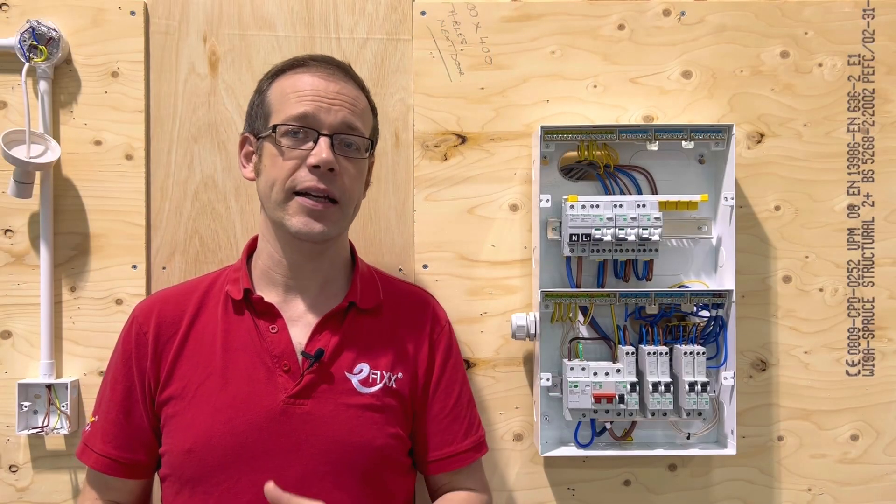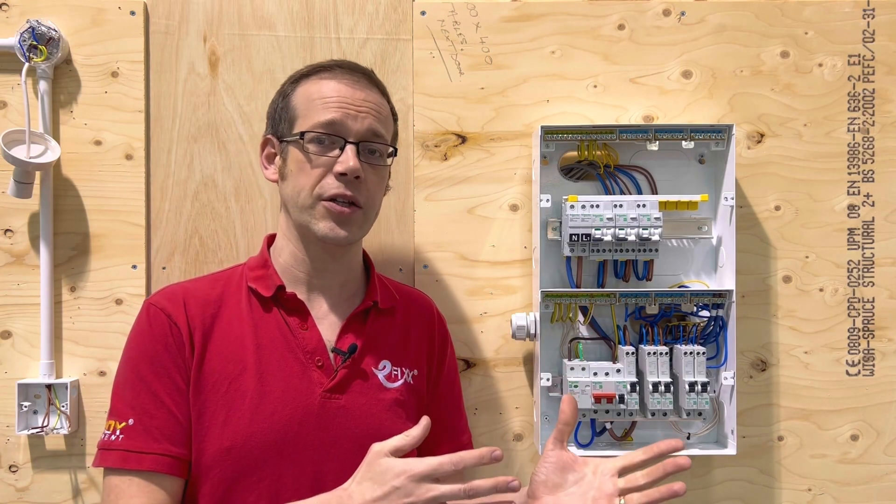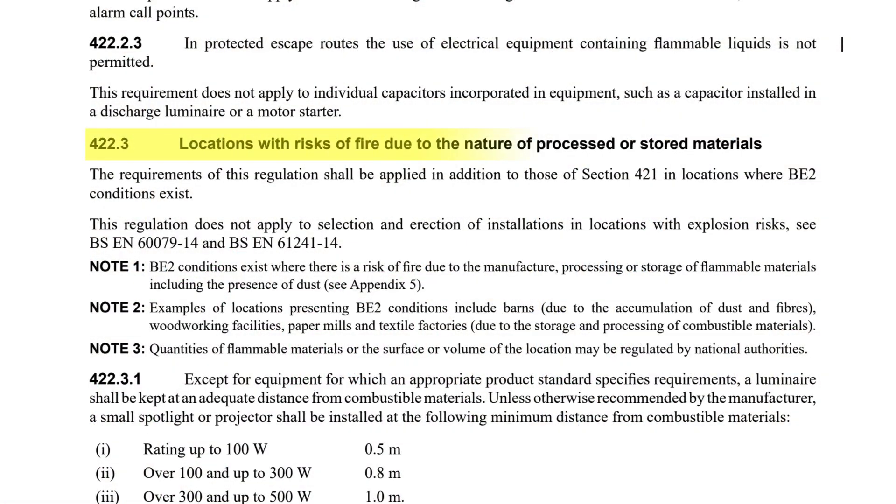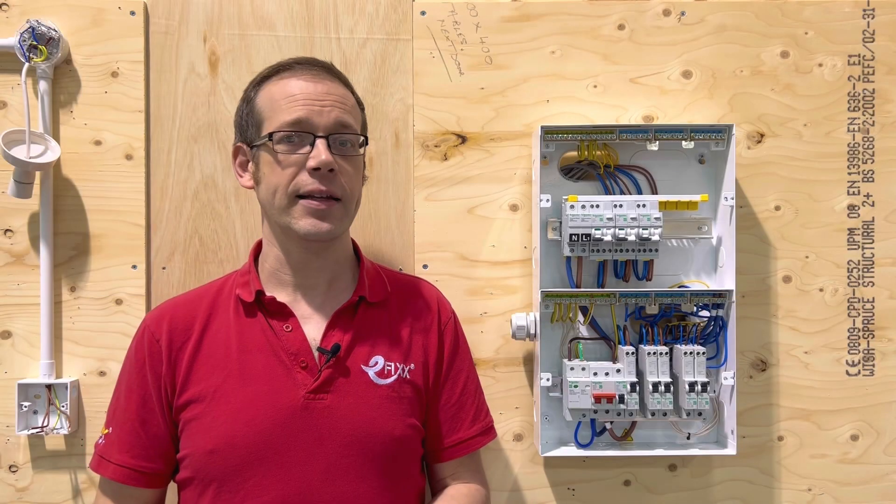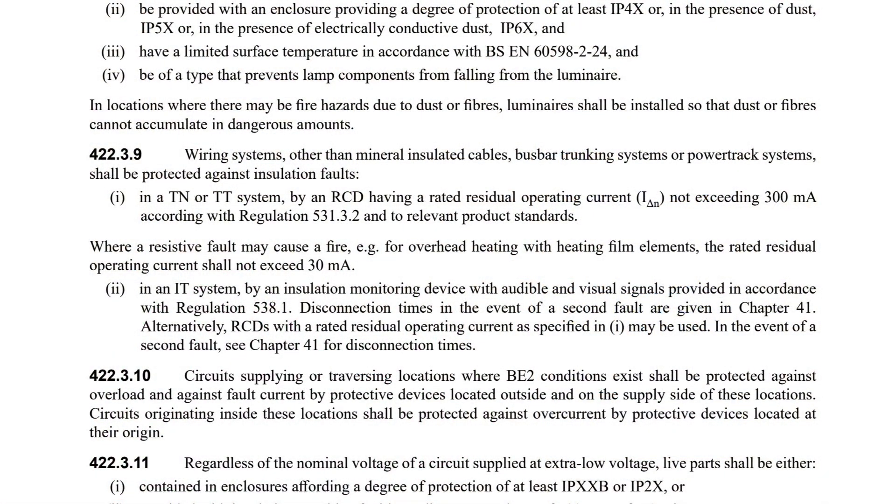Other places that specifically require RCD protection for reasons other than additional or fault protection relate to section 422.3 which is concerned with locations with risks of fire due to the nature of processed or stored materials. According to note two there this may include barns due to the accumulation of dust and fibers, woodworking facilities, paper mills and textile factories due to the storage and processing of combustible materials. In areas like these and similar regulation 422.3.9 states that in these locations wiring systems other than mineral insulated cables, bus bar trunking systems or power track systems shall be protected against insulation faults in a TN or TT system by an RCD having a rated residual operating current not exceeding 300 milliamps according with regulation 531.3.2 and to relevant product standards.